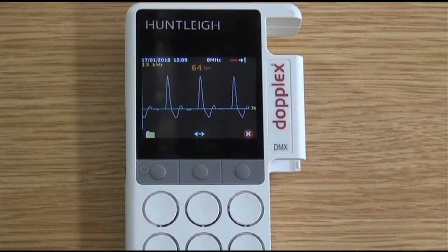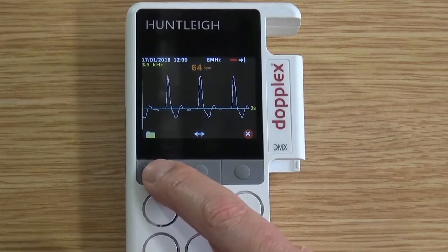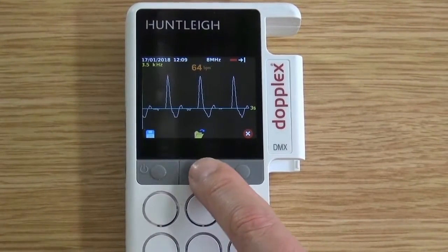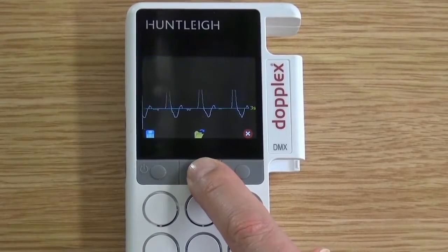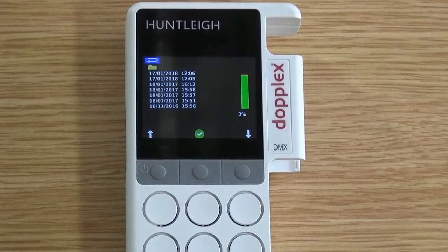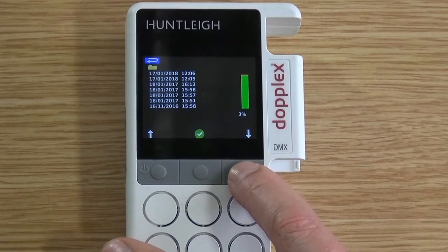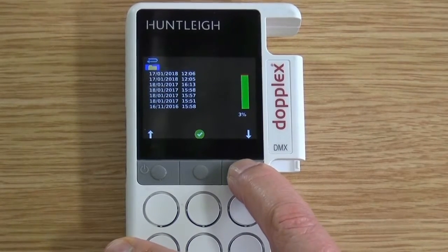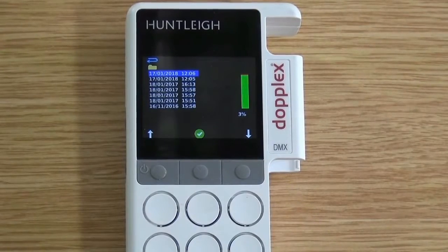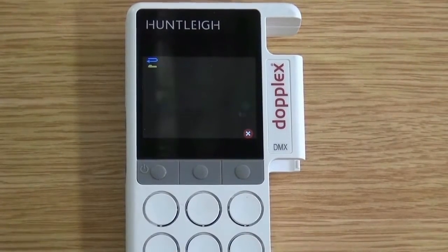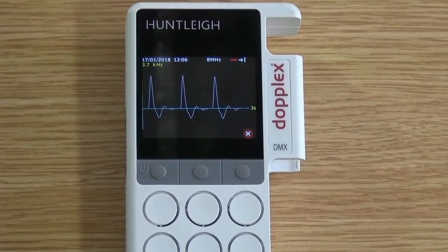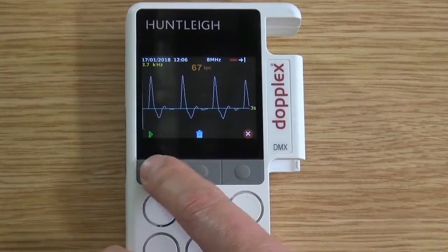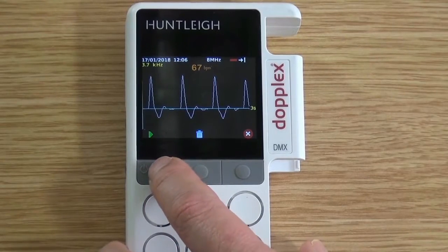To replay recorded traces from the memory card, press the File menu key and then button 2. This opens the folder, where you can see a list of previously stored waveforms in a date and time format. To replay any of these, press the down button arrow and then press green tick. The waveform and sound will then play. To play again, press button 1.